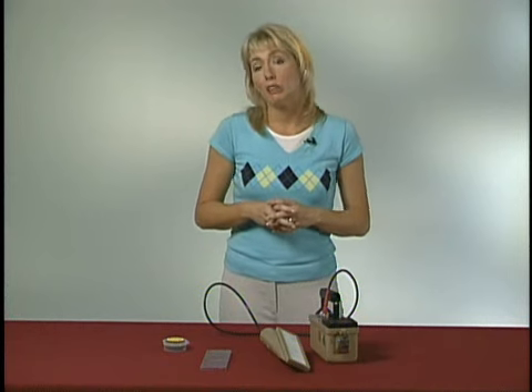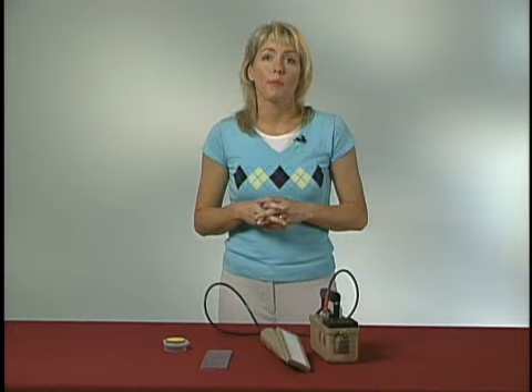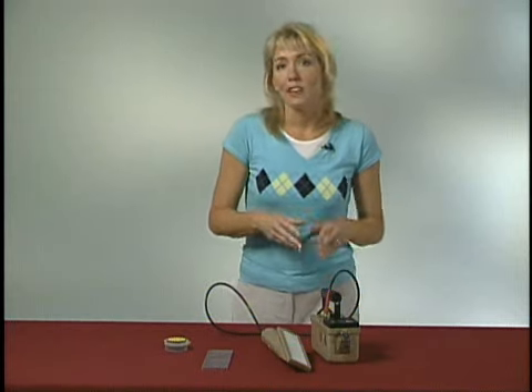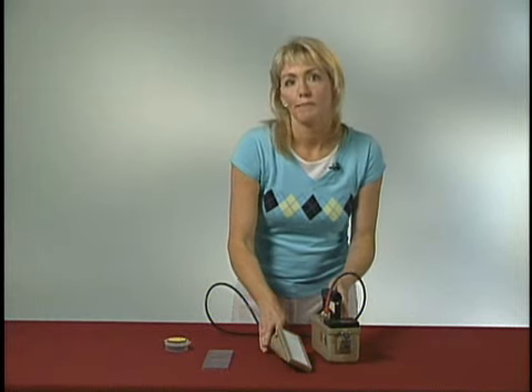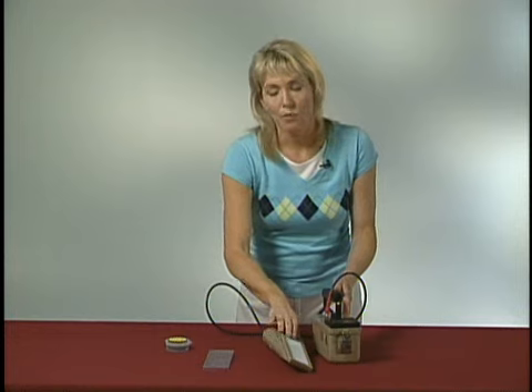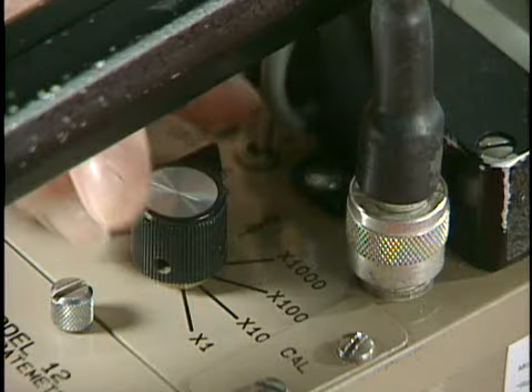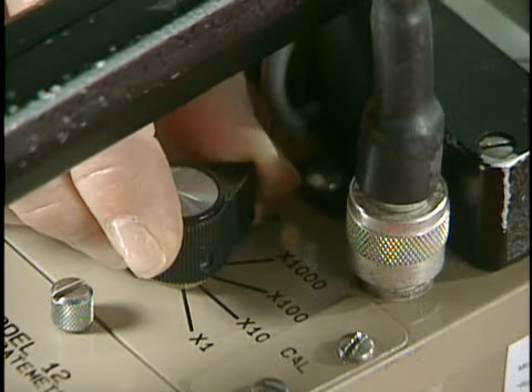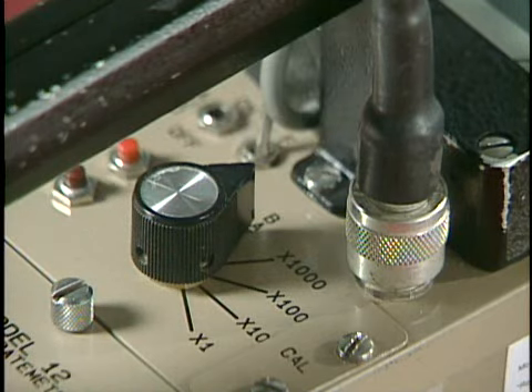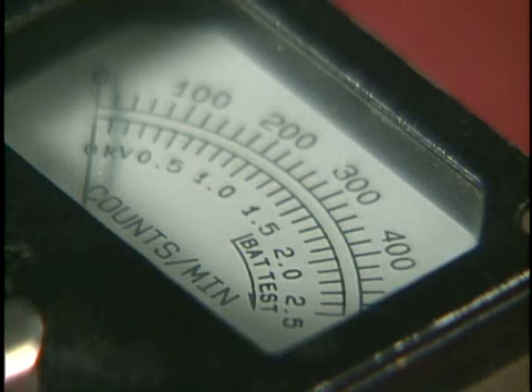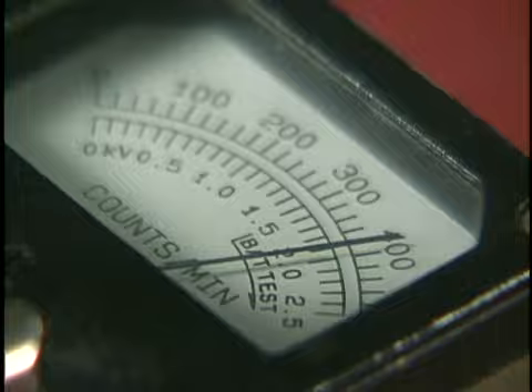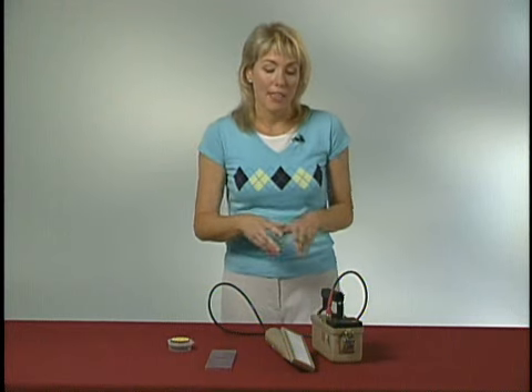As always, you need to make sure that the instrument is working properly before you try to use it. By now, you should be reasonably familiar with how to do this. First, examine the device for visible signs of damage, such as dents in the probe or damage to the window. Next, check the batteries. Again, your meter will either have a range switch that you turn or a button that you push to check the battery condition. If the needle on the meter does not move to the position that indicates the batteries are okay, go ahead and replace them, and then repeat the battery check.